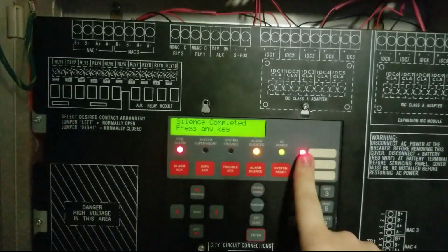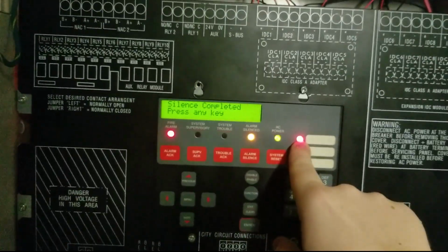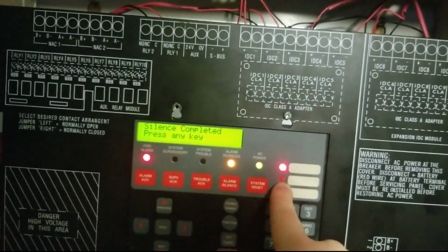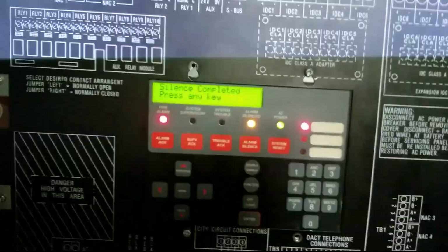Alright. So something I did forget to mention is that these programmable LEDs here, I also changed. So this top one is linked to zone 1, the smoke detector. This middle one is linked to manual evac. And this third one is linked to zone 3, which is this. So yep, these two top ones are red, and this one down here is yellow.